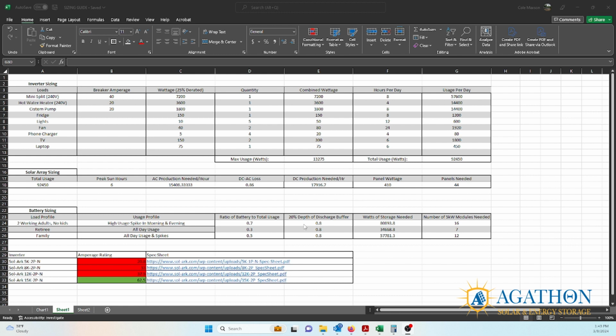You're also not going to have much usage in the middle of the day when you're at work, so you'll want to save more solar energy to use later. That gives a much higher ratio of battery to total solar compared to a retiree. Next, we add a 20% depth of discharge buffer, to make sure you're not discharging your battery too low and causing damage. Finally, with that value, we determine how much storage you need. This number is in watts, not kilowatts. We take that number, in this case 80,000 watts, and divide it by 5 kilowatts, since there are 1,000 watts per kilowatt. So you will need about 16 5-kilowatt modules based on this load profile.